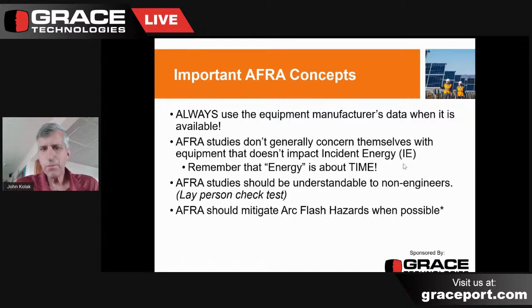If you want to know what 1.2 calories of heat actually is, if you were to take a standard issue candle and light the candle, hold your finger 1 inch above the candle flame for 1 second, that is 1.2 calories per square centimeter of incident energy. And that will be the onset of a second-degree burn. So it's very important to understand that when we're talking about energy, we're talking about essentially how long your finger's in the candle, so to speak. And I'll use that expression more than once in the presentation because it's a good visual to think about.